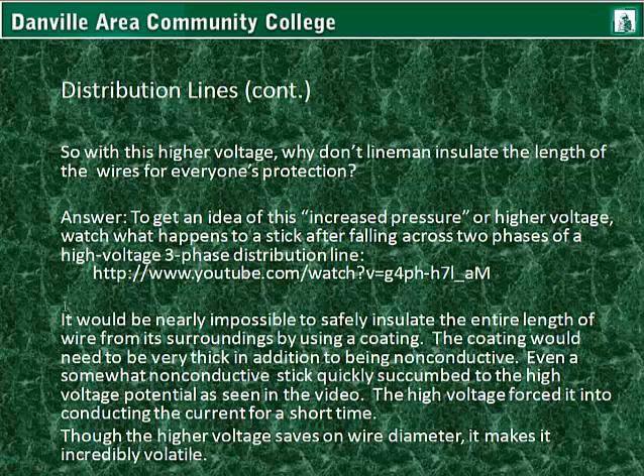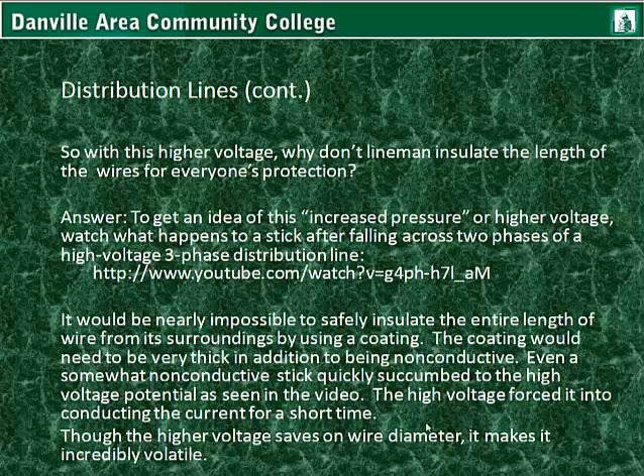After watching this video, you definitely have an understanding of what's going on with this higher voltage. It would be nearly impossible to safely insulate the entire length of the wire from its surroundings by using a type of coating. The coating would need to be very thick in addition to being non-conductive. Even a somewhat non-conductive stick quickly succumbed to the high voltage potential, as seen in the video — the high voltage forced it into conducting current for a short time. Since the coating would be very thick, it would also weigh a lot, and they would no longer be able to hold it on posts — it would be near the ground, which would make it more dangerous. So rather than coating it entirely, they use large glass or ceramic insulators as standoffs on the poles. Though the higher voltage saves on wire diameter, it does make it incredibly volatile.